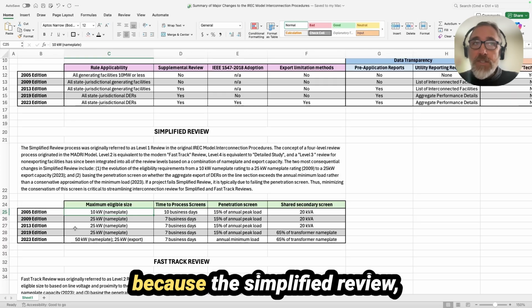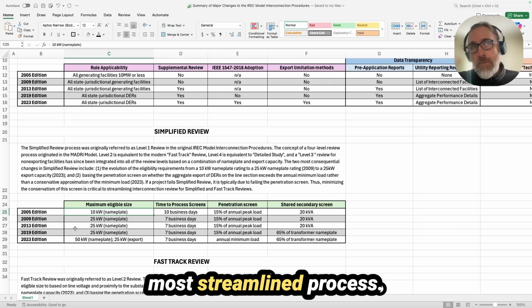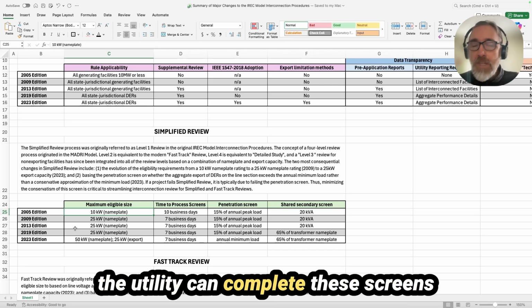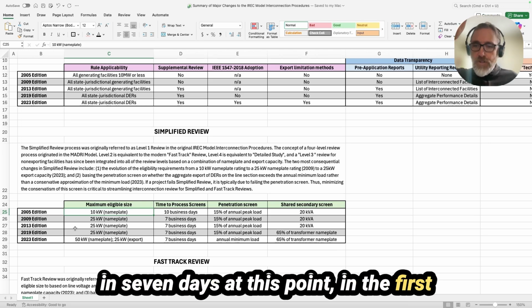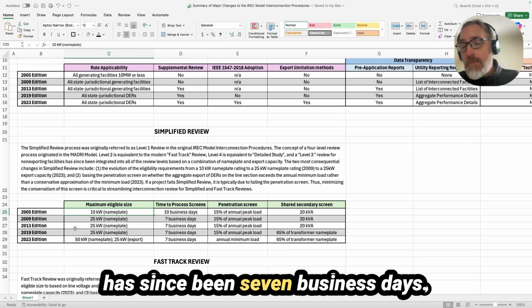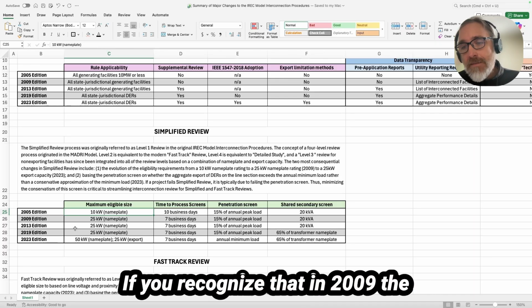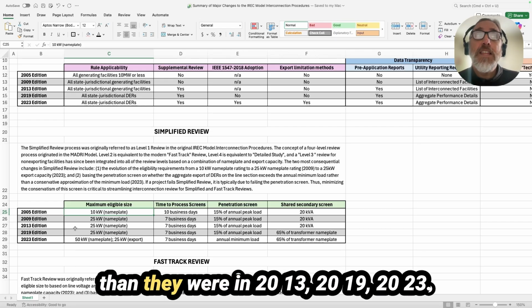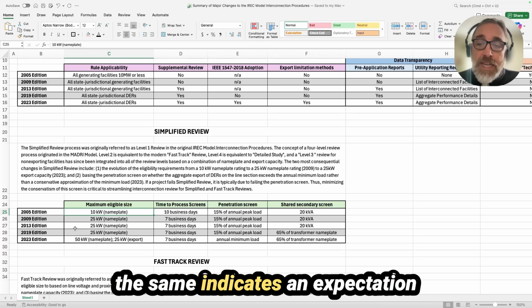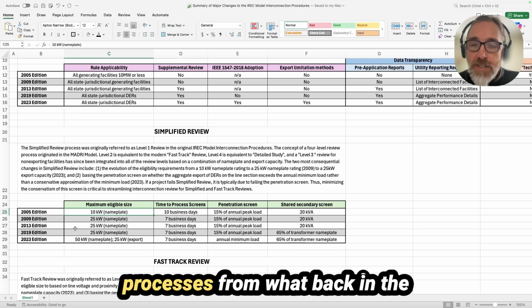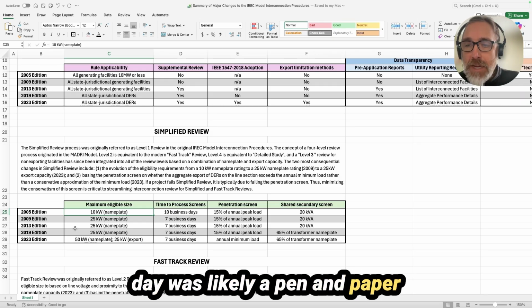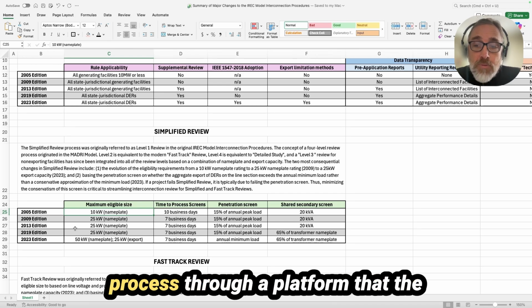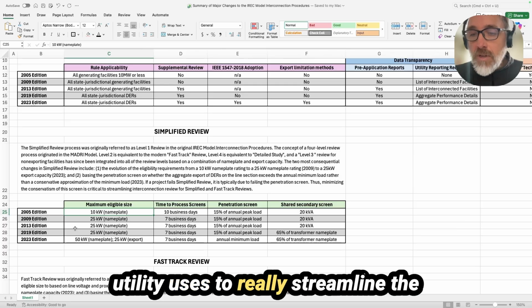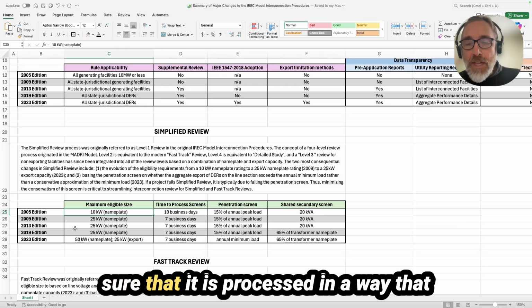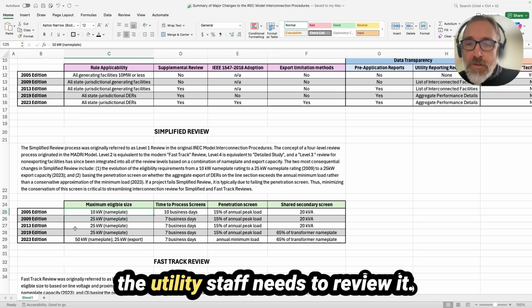This change is important because the simplified review, as the name indicates, is the most streamlined process. As you can see here, it's expected that the utility can complete these screens in 7 days at this point. In the first edition, it was 10 business days, and it has since been 7 business days. If you recognize that in 2009, the number of applications that were coming in for utilities were far less than they were in 2013, 2019, 2023. This 7 business days remaining the same indicates an expectation that the utilities are adapting processes from what back in the day was likely a pen and paper application to today an automated process through a platform that the utility uses to really streamline the paperwork that comes in and to make sure that it is processed in a way that minimizes the amount of time that the utility staff needs to review it.